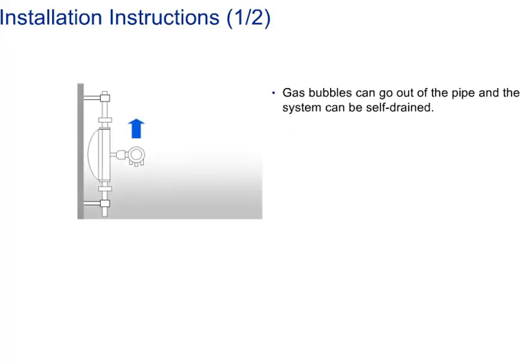The optimal installation orientation is a vertical installation with upward flow. Gas bubbles can escape from the meter and pipework, and the system is inherently self-draining.